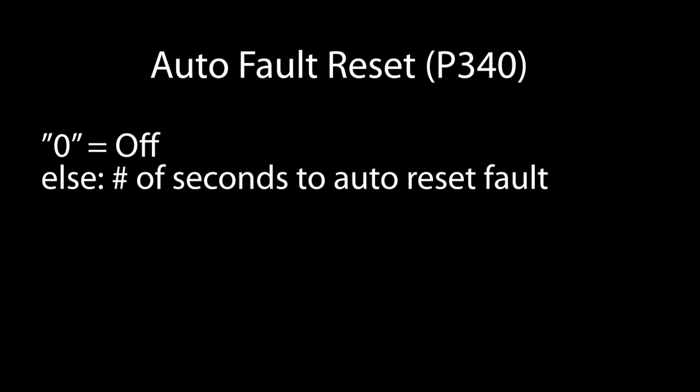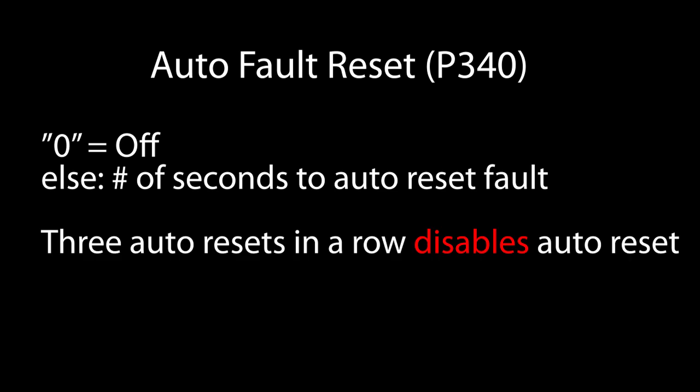Finally, remember that the drive has an auto reset function for faults. It defaults to 0 which is off, but if you change it to a non-zero time, the fault will auto reset after the number of seconds you specify. And if the fault auto resets more than 3 times within 30 seconds after a reset, it will shut the drive down and it won't auto reset anymore. That way an unattended drive won't sit there resetting itself over and over indefinitely.